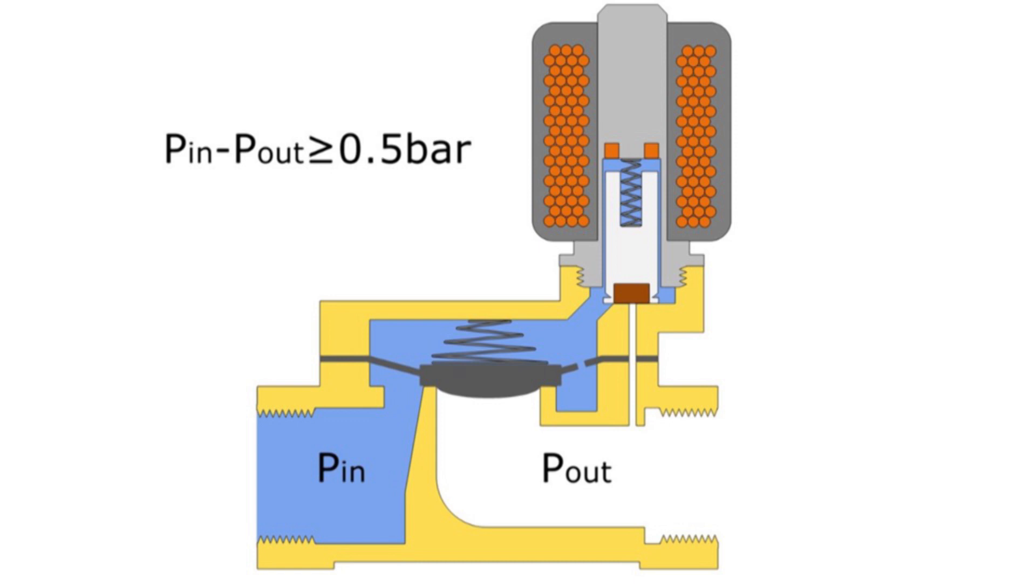Indirect operated valves require a differential pressure of typically 0.5 bar to open. Indirect operated solenoid valves are also referred to as servo or pilot operated.